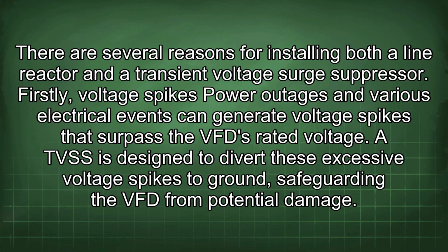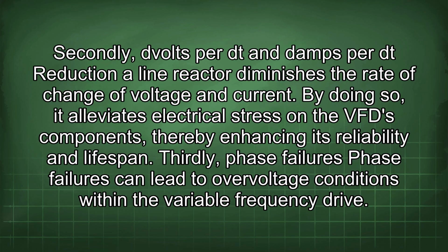Firstly, voltage spikes. Power outages and various electrical events can generate voltage spikes that surpass the VFD rated voltage. A TVSS is designed to divert these excessive voltage spikes to ground, safeguarding the VFD from potential damage. Secondly, dV per dt and dI per dt reduction. A line reactor diminishes the rate of change of voltage and current. By doing so, it alleviates electrical stress on the VFD components, thereby enhancing its reliability and lifespan.